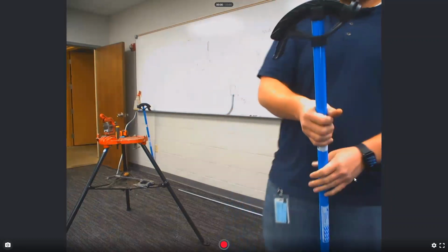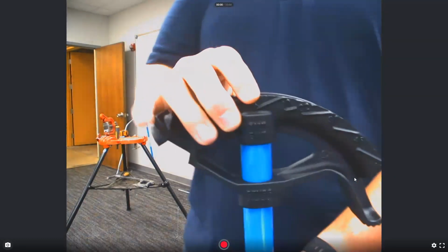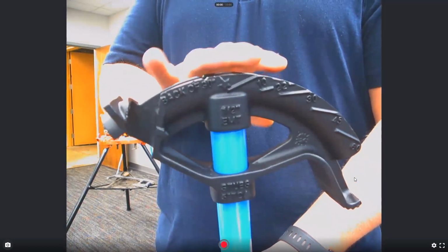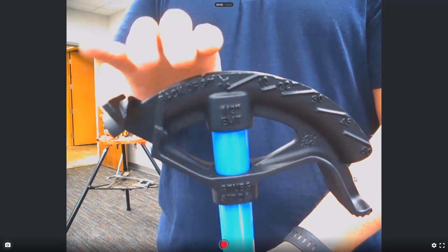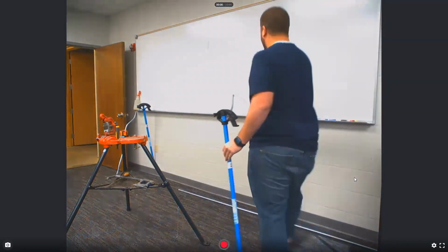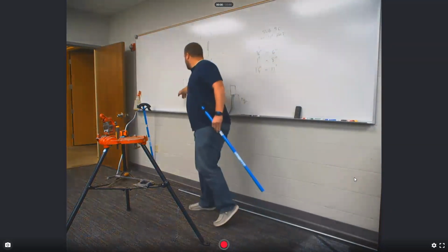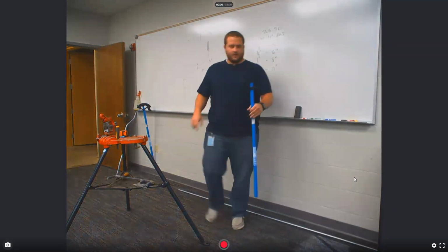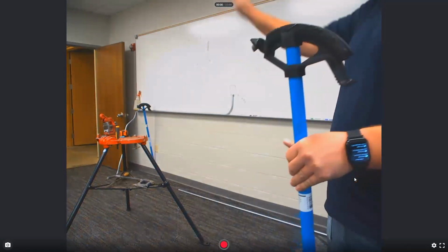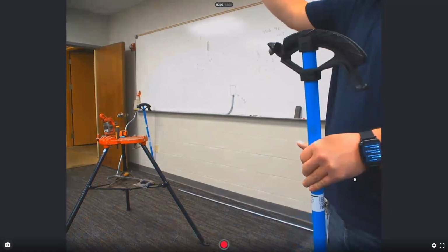The tip of the star indicates the back of a 90-degree bend. So if I measure that distance from the end of this 90 to the end of this coupling, put that mark on the star and bend it up, it should bend right up to the outside of that coupling.